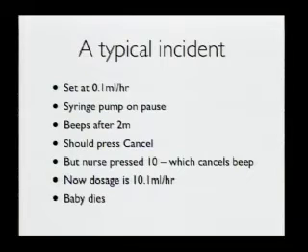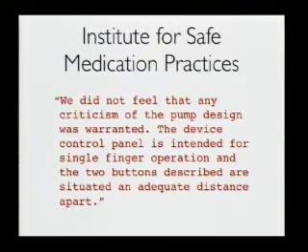It's very sad. The Institute for Safe Medication Practices wrote a report on this incident, and a bit I pulled out of the report said, we didn't feel that any criticism of the pump design was warranted. The device control panel is intended for single finger operation, and the 2 buttons described are situated an adequate distance apart. In other words, what I would view as a design error has been treated as an operator error. The operator, in this case the nurse, is the fall guy. They either get sacked or they get sent on retraining courses or whatever. But rather than fix the design problem, the user is blamed. They made the mistake.